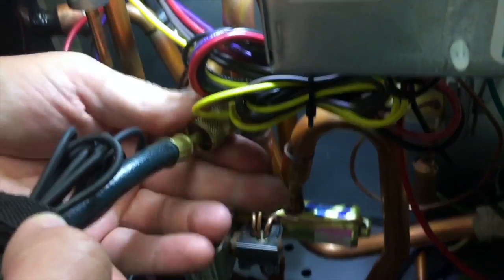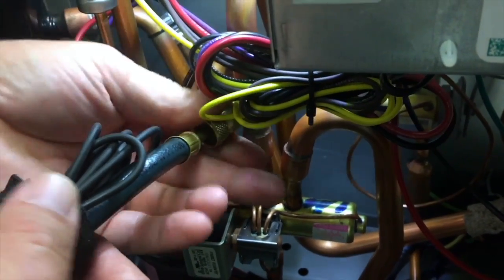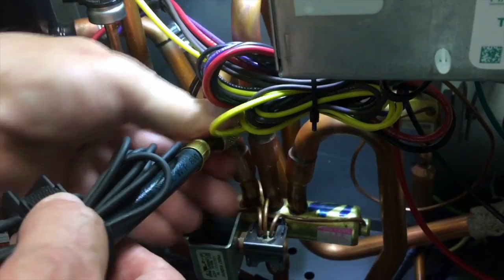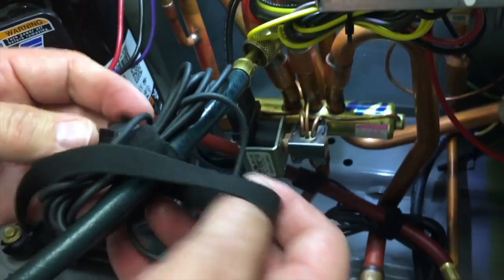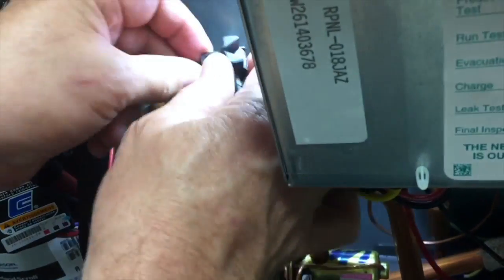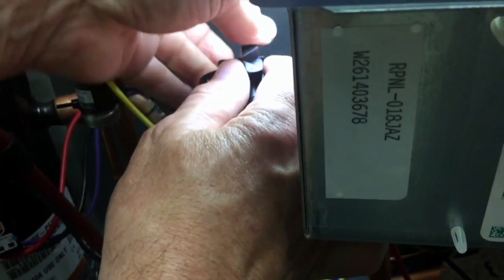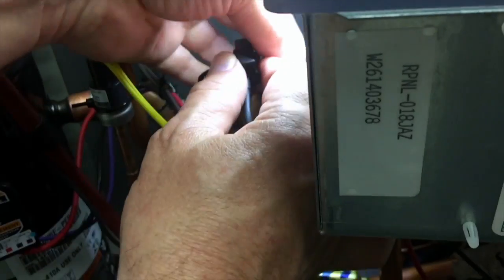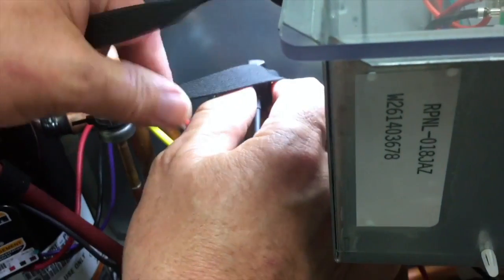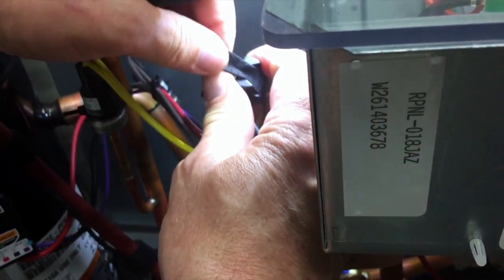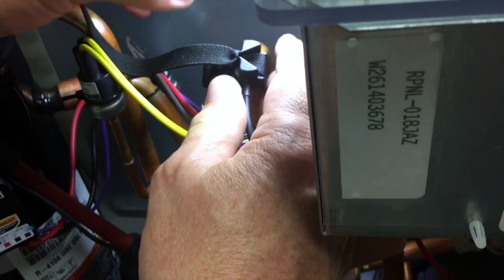The new refrigerants, especially like 410A, contain PoE oil, and PoE is very hygroscopic. So we want to make sure we're not getting moisture in the hose when it's disconnected. You always want to keep your hoses parked nice and tight. We'll just put this through and pull it through the V and pull it snug.